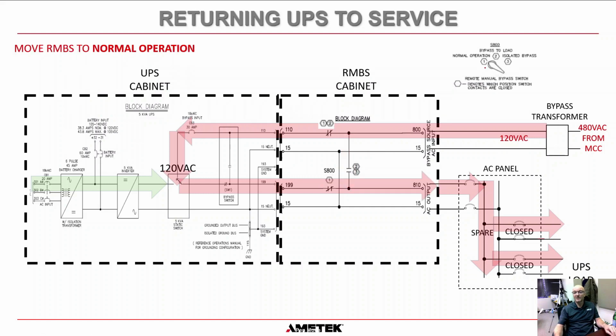So when we go to position 1, we're still in static bypass, but we are now in normal operation on the RMBS. Power flow now goes through the UPS, through the static switch, and back out this way here to our load circuits. And then the final thing that we have to do is move the static switch to the inverter to load position, and we do that by pressing the inverter to load push button on the UPS, and now we're back in normal operation.